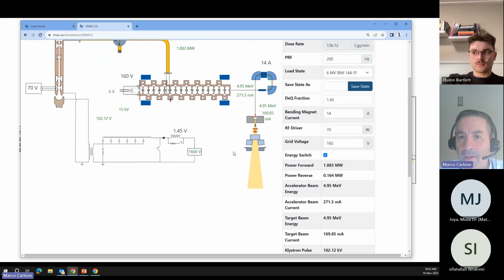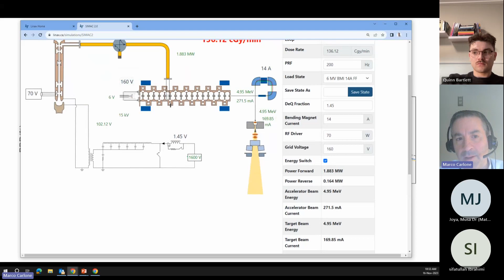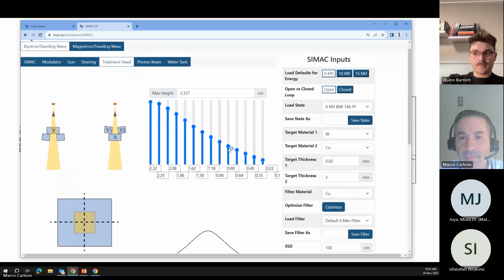So now we have a very low energy beam, because we've dropped the bending magnet current quite a bit. I've configured the grid voltage in order to reduce the energy, and that's matched with the bending magnet. When we look at our treatment head screen now, the profile again looks quite a bit different. In this case, it's over attenuating at the center and under attenuating at the sides, because the flattening filter is designed for 6 MV, not about 5 MV, and so it attenuates the 5 MV beam more at the center. At the sides of the beam, the flattening filter is very thin and doesn't have much of an effect, so you have this strange shape, with an over attenuated beam at the center.